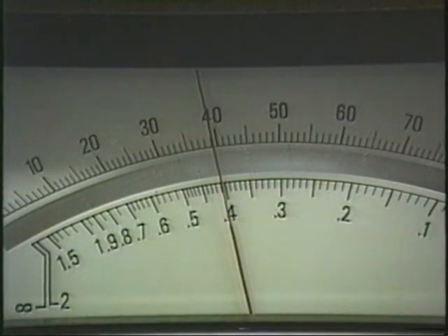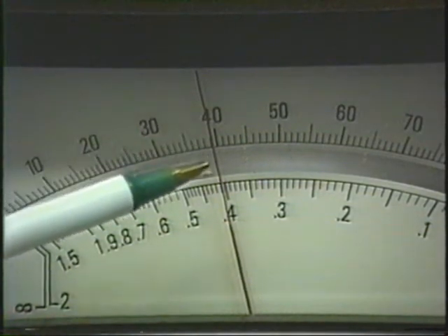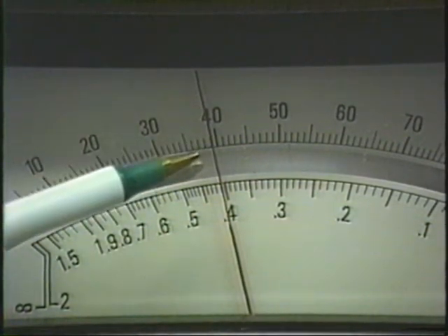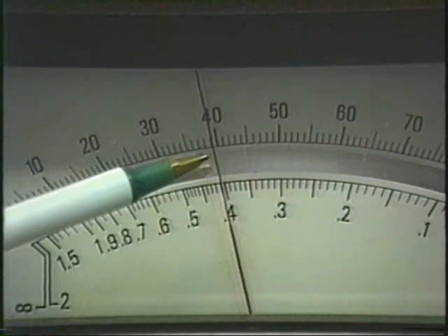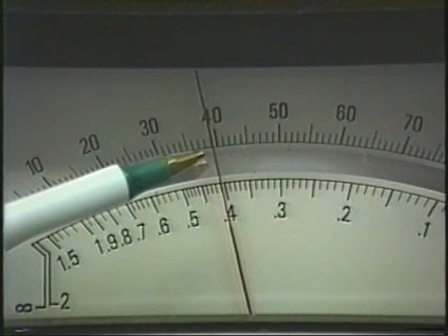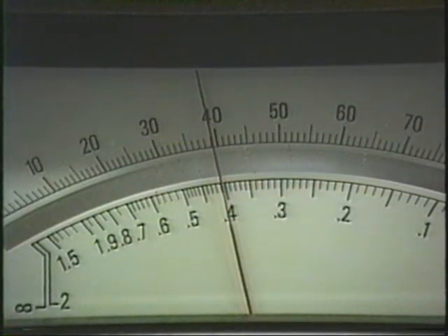All right, here we have another sample in the spectrometer, and if we do the reading, we can see that it is reading 39.2 or 39.1% transmission. Now you see that you cannot see the reflection of the needle in the mirror here. You see there's a mirror, you can see the reflection of the pen, but you can't see the reflection of the needle. That means that you're looking directly on, and this is a correct reading. If you see the reflection of the needle in the mirror, you have to move your head. And if you still see it, you should close an eye.